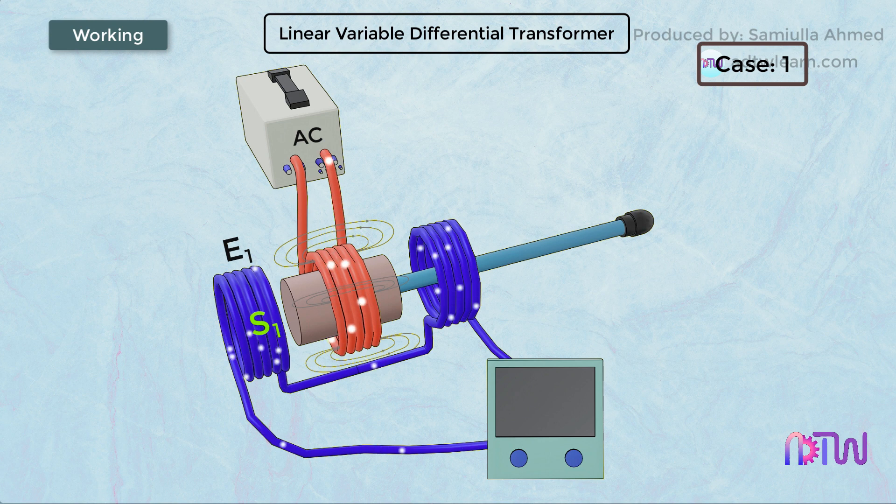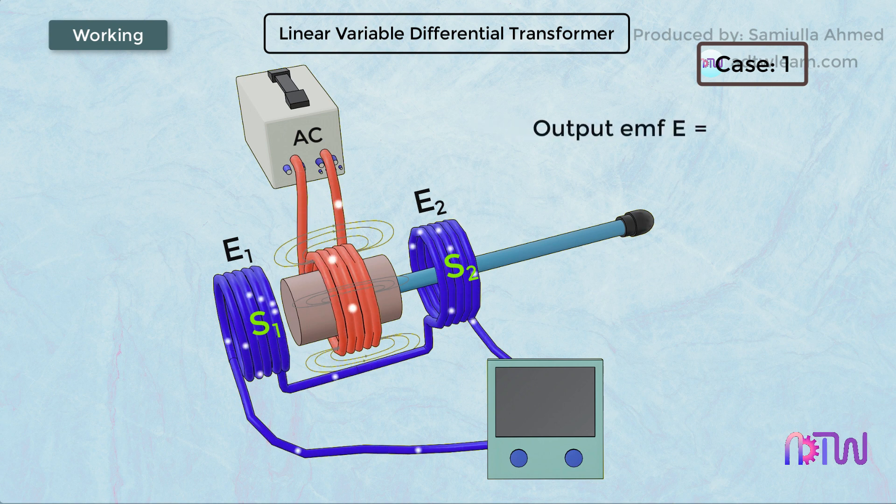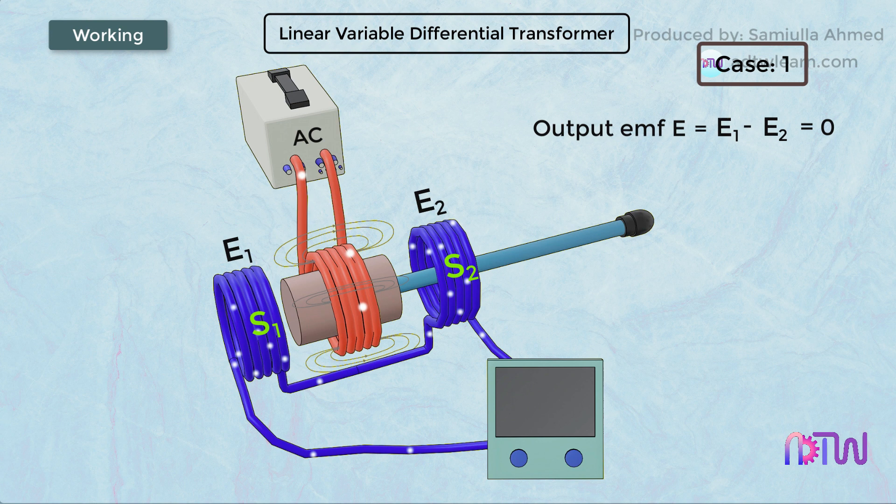That is EMF E1 in the secondary coil S1 and EMF E2 in the other secondary coil S2. Since the two coils are equal in turns but of opposite magnitude, therefore this EMF generated will cancel each other and the net EMF generated will be null. That is, output EMF E equals E1 minus E2, which will be equal to zero.